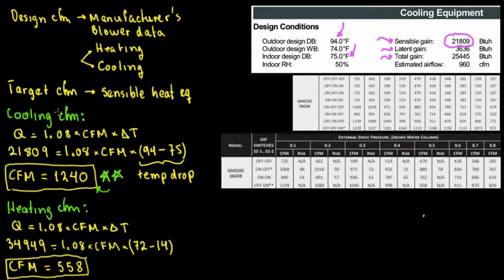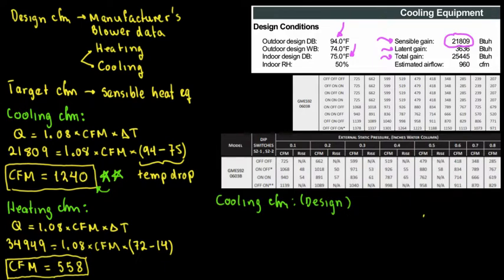Now we go to the manufacturer's data to find the design CFM for cooling. When looking at the blower data — also called performance data or fan performance data — CFM is paired with external static pressure (ESP). So whenever you state a CFM, you also need to state the static pressure at that point.